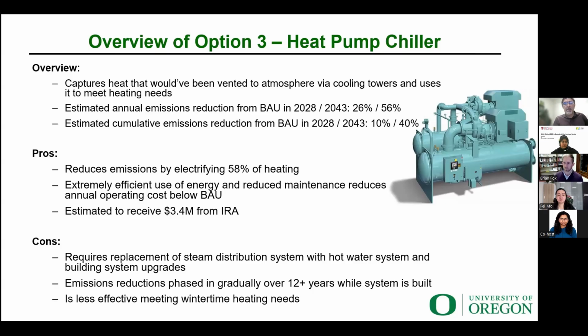The cooling that you're doing in the buildings can be captured and repurposed as heat to take care of simultaneous heating and cooling loads you may have. We did a study and saw we had significant simultaneous heating and cooling. So installing a heat pump chiller connecting those lines increases your efficiency dramatically, linking the two systems instead of running them independently.